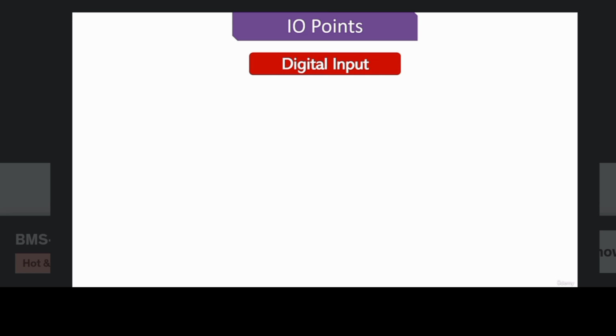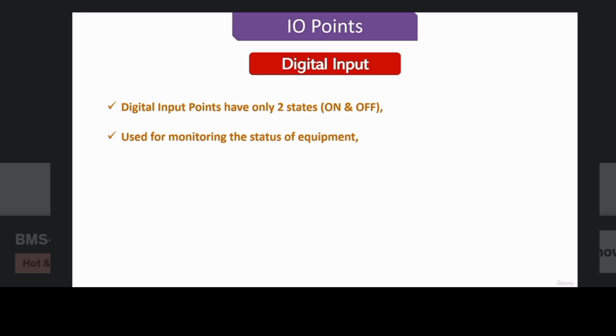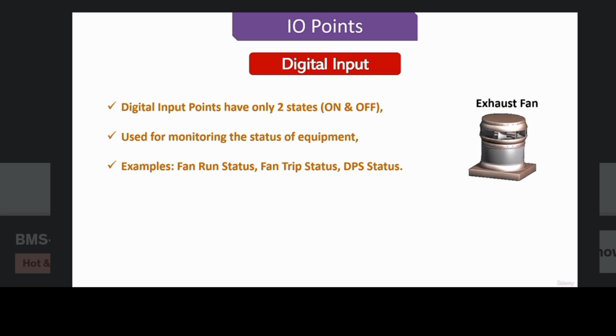Let's discuss digital inputs. Digital input points have only two states, which can be either on or off. These points are used for monitoring the status of equipment. Examples of digital input points can be fan run status, fan trip status, status from a differential pressure switch, and status of a pump.